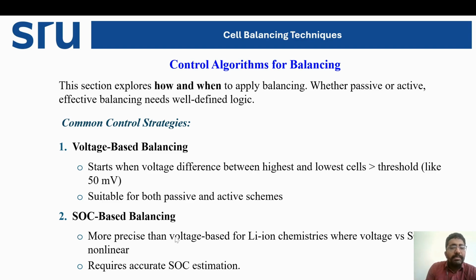Next is state of charge, or SOC based balancing, which is more precise compared to voltage based balancing. SOC based has better features since it's more precise, especially for lithium ion chemistry where voltage versus SOC is non-linear. The disadvantage is that it requires accurate state of charge estimation. Between these two, SOC based is the more preferred method, being more precise than voltage based for lithium ion chemistry.